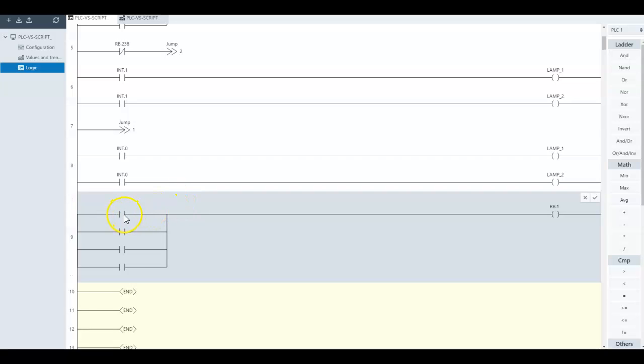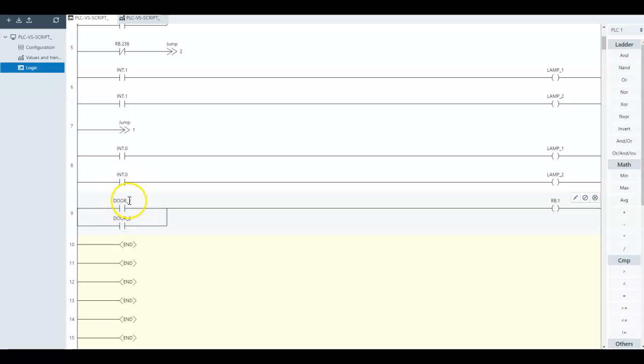and then we can add the parameters. So basically here we can select, this is the binary input number 1. This should be again the binary input number 2. Select channel number 2. And we select here where the result will be stored, which in this case is the result bit number 1. We click the OK checkbox here, and automatically you will notice that the input, if we hover on top of the door 1, which is a label, will be showing you the parameter here. This one doesn't have any label, that's why it's not doing anything.